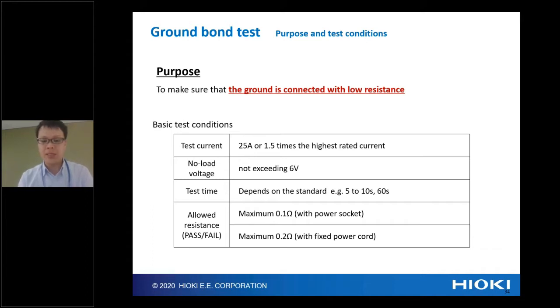The test time depends on the standard. In most cases, we can say 5 to 10 seconds or 60 seconds. And the allowed resistance, pass or fail: maximum 0.1 ohm if we combine with a detachable power cord, and maximum 0.2 ohm with a fixed power cord.